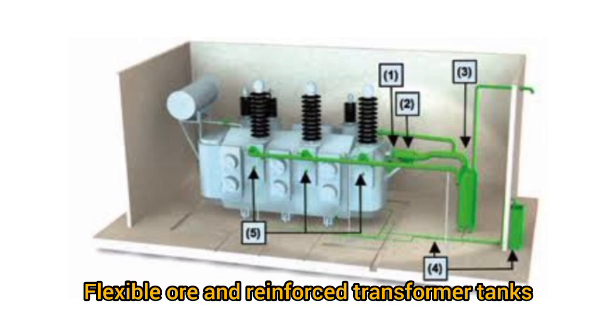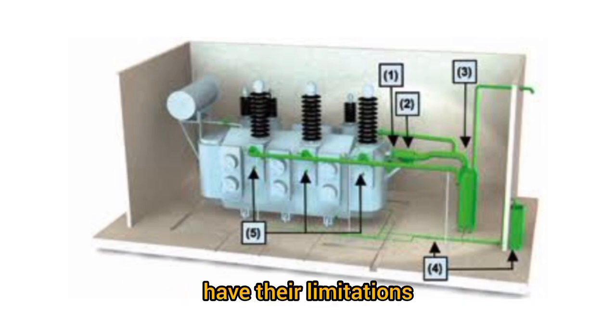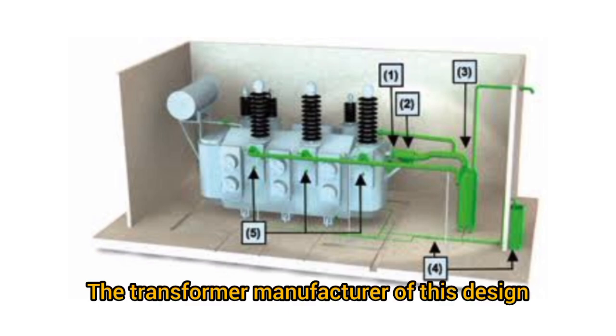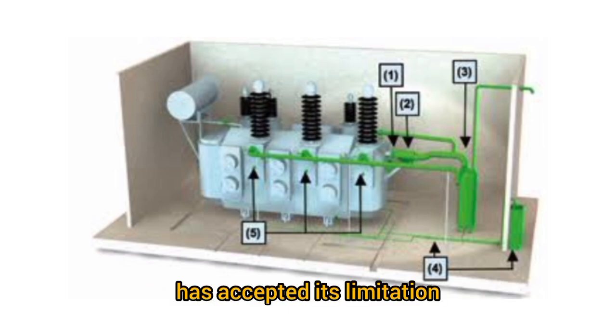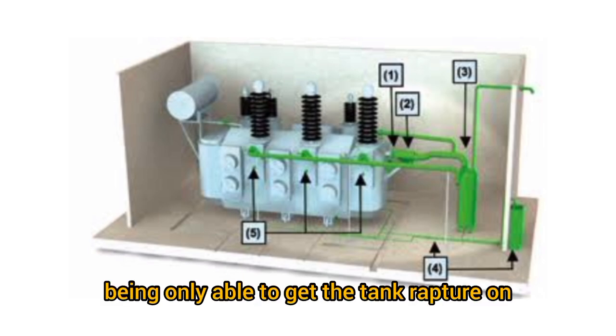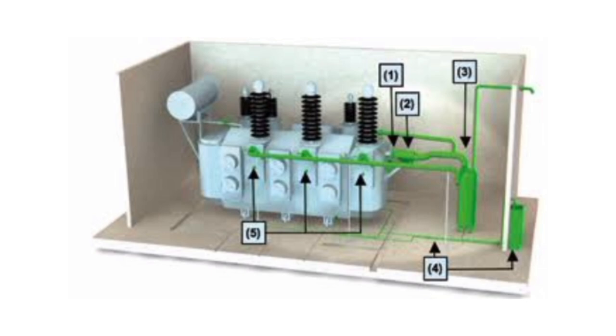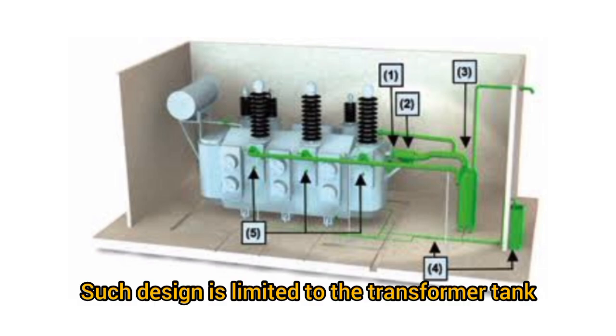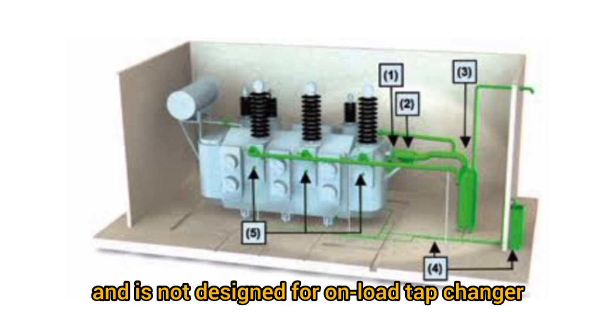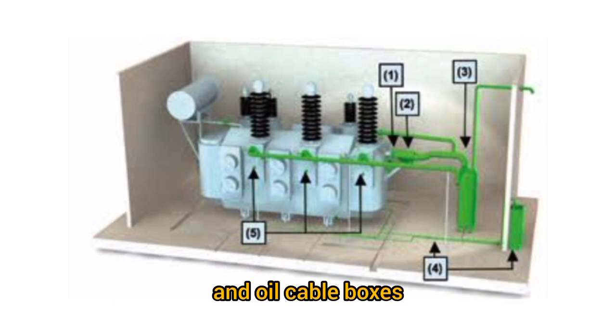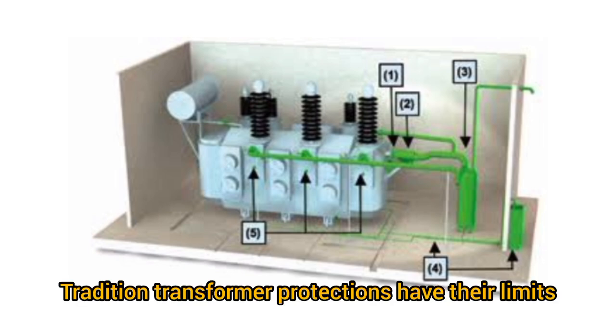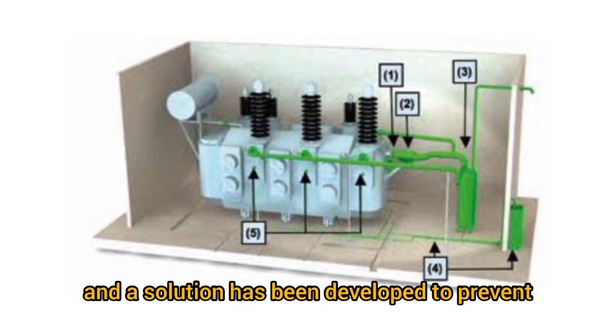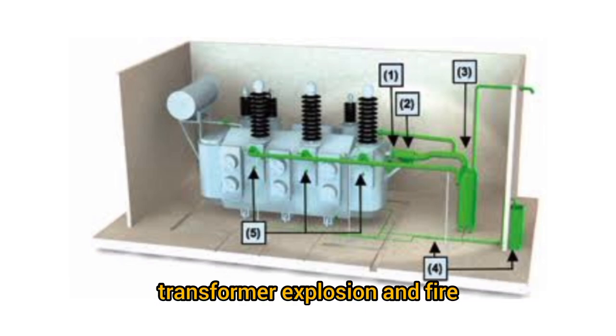Flexible and reinforced transformer tanks have their limitations. The transformer manufacturer of this design has accepted its limitation, being only able to get the tank rupture on the top of the transformer. Such a design is limited to the transformer tank and is not designed for the on-load tap changer and oil cable boxes. Traditional transformer protections have their limits, and a solution has been developed to prevent transformer explosion and fire: the fire water spray system.